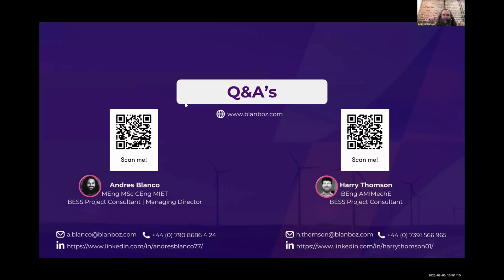Yeah, that's free consultancy services now - no, just kidding. We like pushing the suppliers, and I hope we don't have any battery supplier here so we don't reveal all our secrets. Technically speaking it depends on your project and configuration, but the most standard figure, you can start from 87% round trip efficiency at the point of connection, regardless of medium voltage or HV, including the auxiliary loads. Then you can adjust that if you move the point of reference to where the actual battery is interconnected - you can have 87 or 85%, and the 87% is a bit for negotiation, but normally it's agreed contractually at 87%. That's if you mean the round trip efficiency of the overall project. If you mean the round trip efficiency of the battery container only, the DC side, sometimes also called round trip efficiency, you can see anything between 92 and 95%, depending on the supplier.